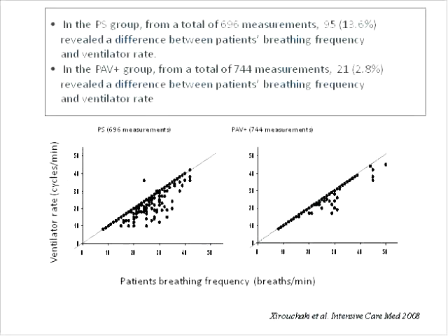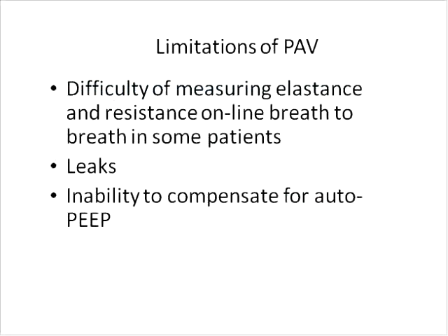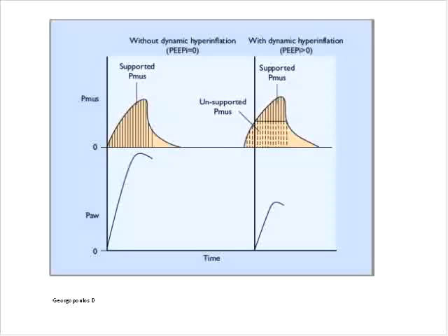Limitations of PAV. It does have to measure online elastance and resistance, which seems to be taken care of at this point. Leaks can really complicate PAV and make it difficult to use. And the weakness of PAV, compared to NAVA perhaps, is that it can't overcome auto-PEEP, because PAV can't do anything until the breath is triggered. So in terms of work of breathing, if your work of breathing is caused by intrinsic PEEP, it's not going to be relieved by PAV unless it helps reduce the intrinsic PEEP by preventing air trapping and auto-PEEP.